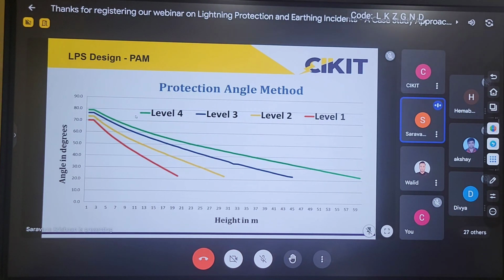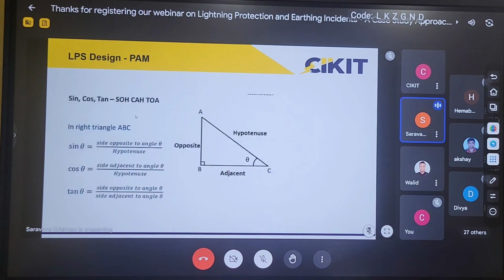From the angle, I have to calculate the value of the radius of protection. For the angle, we can use the tan theta formula. We know that tan theta is the opposite side divided by the adjacent side. In our case, theta is at the top of the air terminal, so from A to C is this angle. From this formula, I can calculate the radius of protection. We know the height of the air terminal, and from the graph we know the value of theta also.